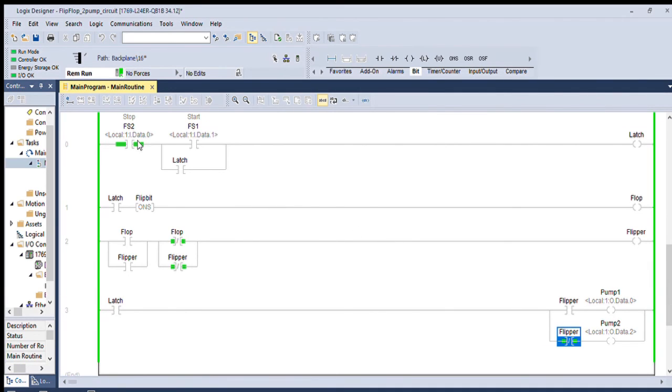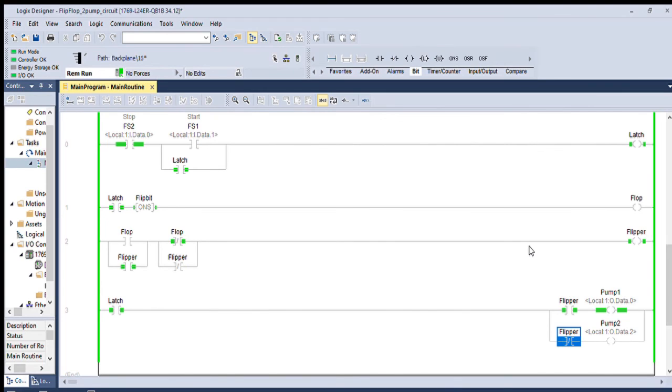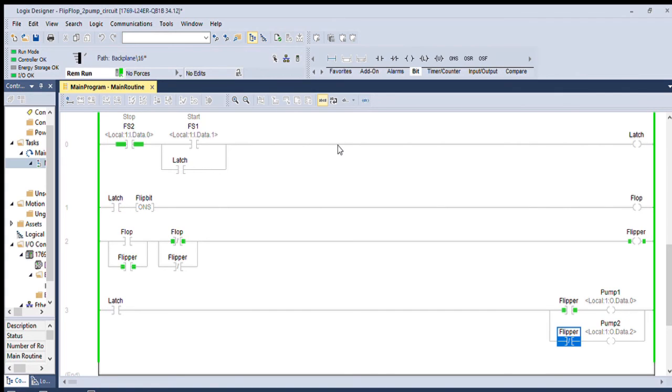So since FS2 is closed, when FS1 here triggers, my latch will come on, that'll hit the one shot. That'll flip the flipper and should turn on pump one is what it should do. Sure enough, it does. We can see here, pump one is on. Now I'm going to stop it, which will disable all the latches. And then when I restart it, the latch will hit the one shot and flip this sequence here.